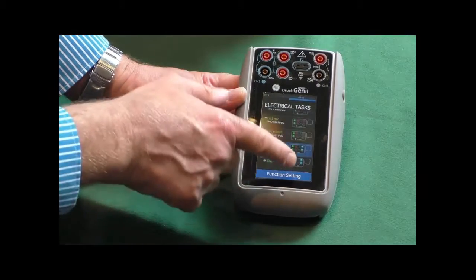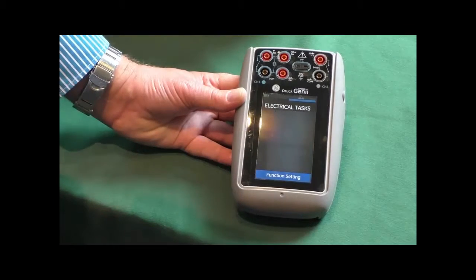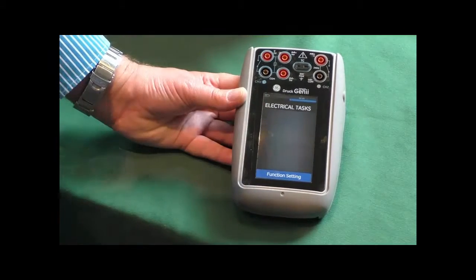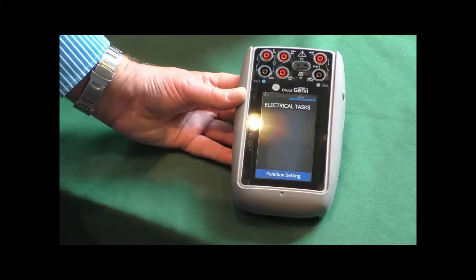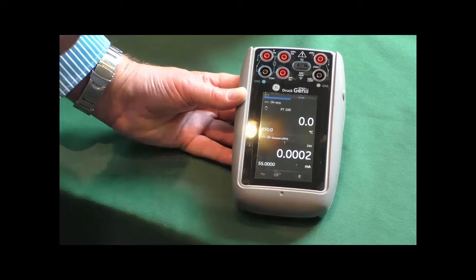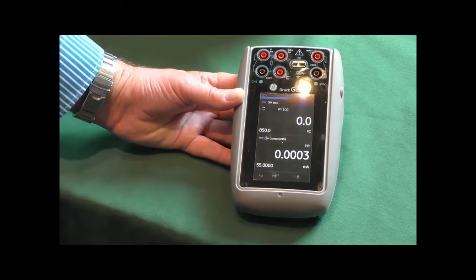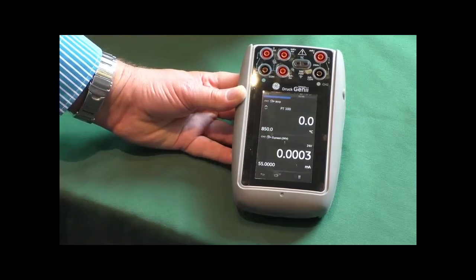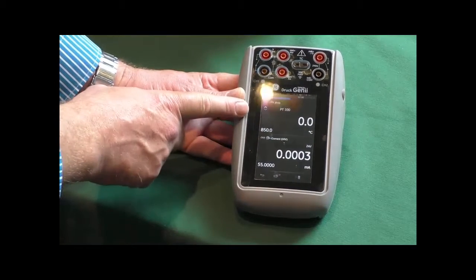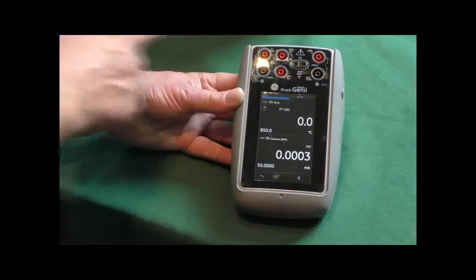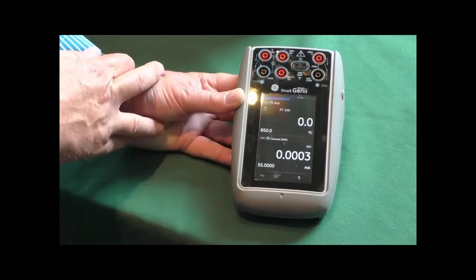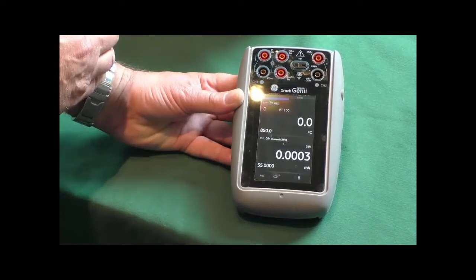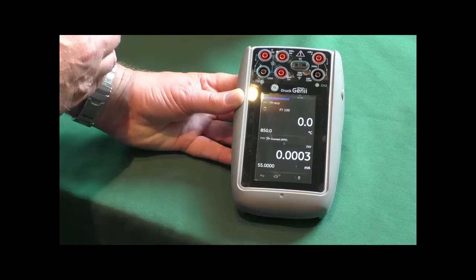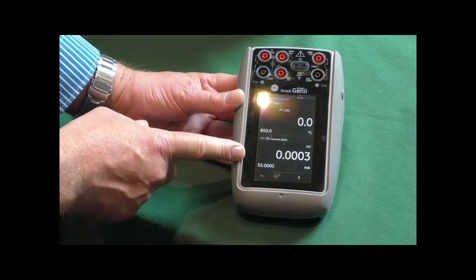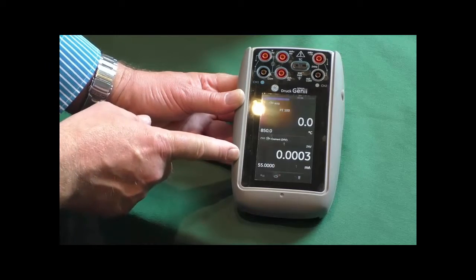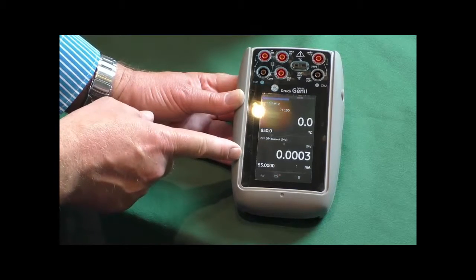We can actually select these as well and put them into our favourites menu. So when you go into your favourites, if they're tasks that you use quite commonly, then you don't have to go and scroll through all the different tasks. You've just got your favourites already set up. So at the moment it's shown at the top here we have degrees C. So this is going to be where I'll simulate the RTD resistance into the transmitter. At the bottom here we have our milliamp output from the transmitter, which I will connect shortly.